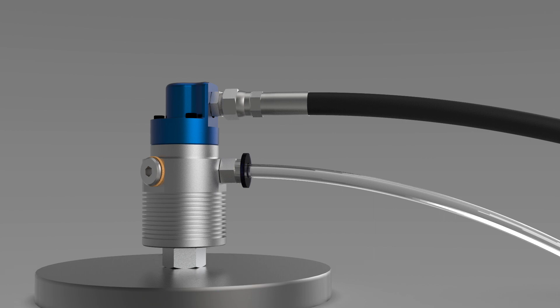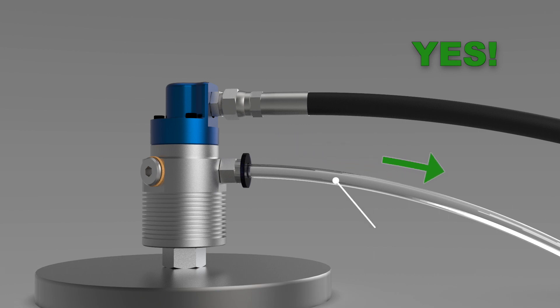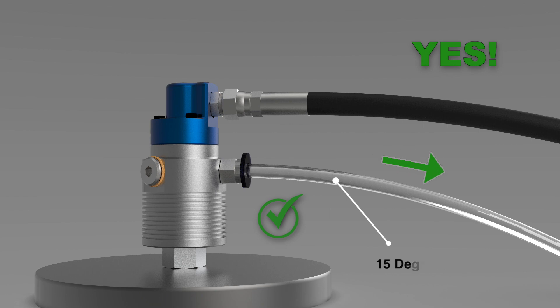Due to gravity, drainage always flows down. For this reason, the drain line always must slope continually down at an angle of at least 15 degrees.